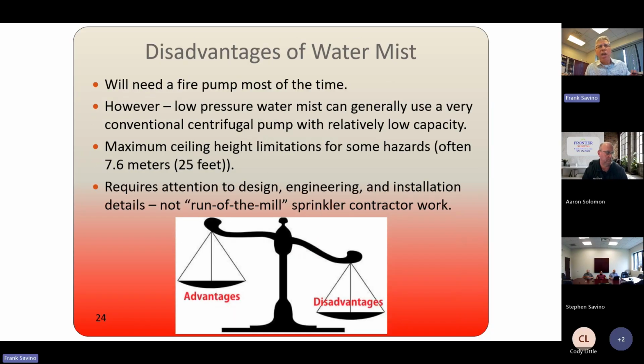Okay, some of the disadvantages: you will need a fire pump most of the time, because even for a low pressure water mist system, you're dealing with a minimum of about 120 PSI at all your nozzles. And you're probably going to do a little more than that, to account for friction loss, et cetera. But with low pressure, you can use a conventional centrifugal pump with relatively low GPM capacity. There is a maximum ceiling height for some of the hazards, like in data halls, 25 feet. And you do need attention to design and engineering. People that are just in the sprinkler business would really need to be trained. So this is really more of a special hazard kind of design.